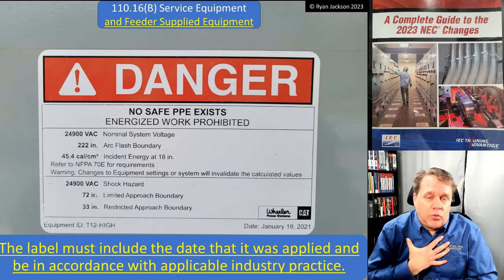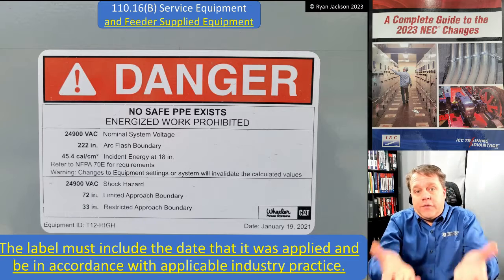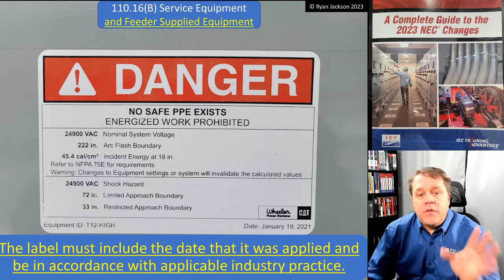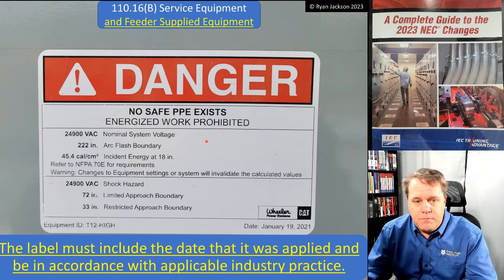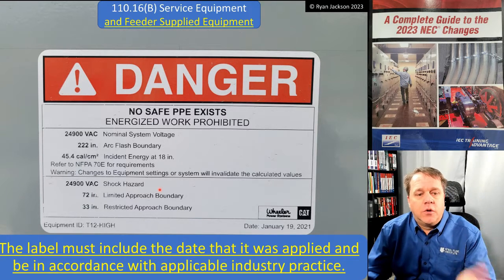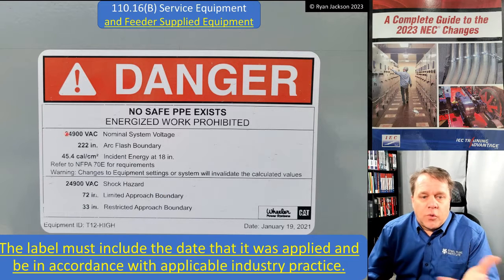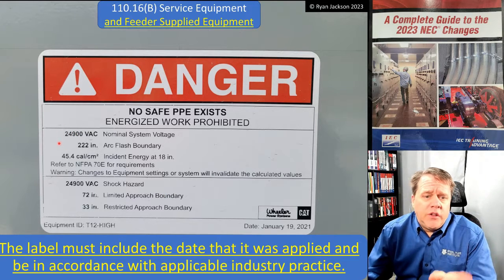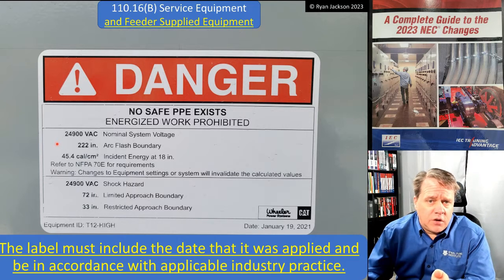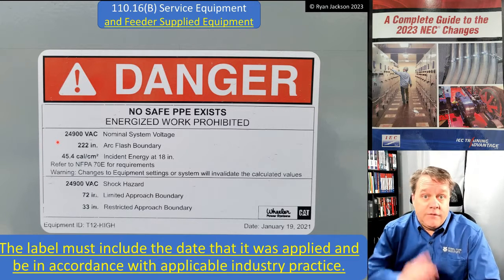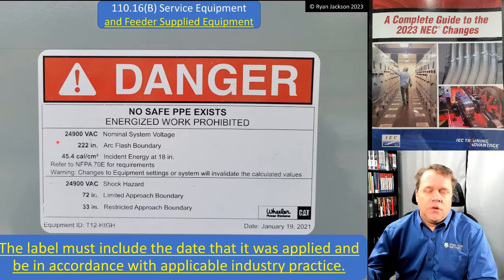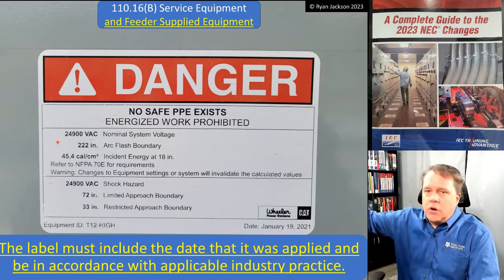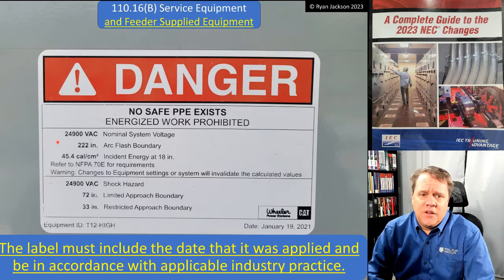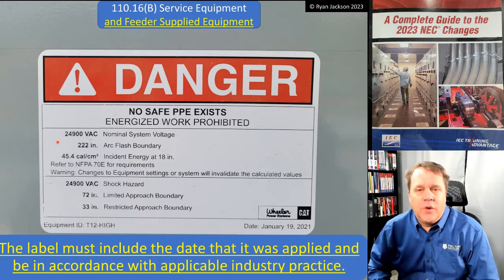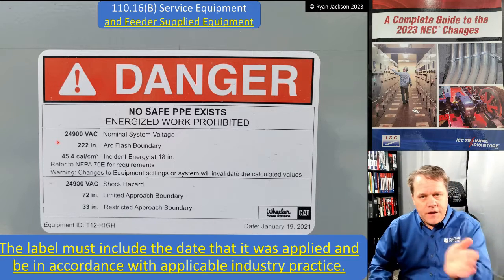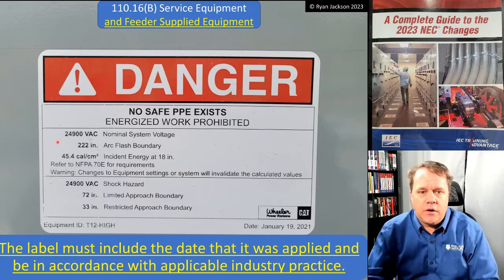I think we're all going to agree that what they're trying to say is an arc flash label is something like this, right? Something where it has the voltage and the arc flash boundary and the incident energy and the voltage and everything else, right? So 25,000 volts, basically. 222 inches is the arc flash boundary. Two things about that. Number one, if you're in the business of making these labels, don't tell me inches if it's more than 12 inches. Tell me feet and inches. I don't know how many feet 222 inches is. That doesn't help anybody. All right, so feet and inches. Don't make me get my calculator out and everything else.